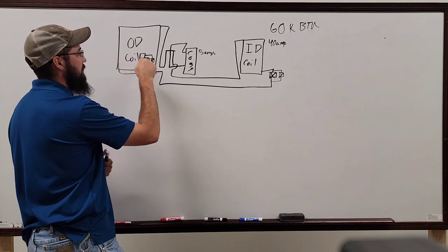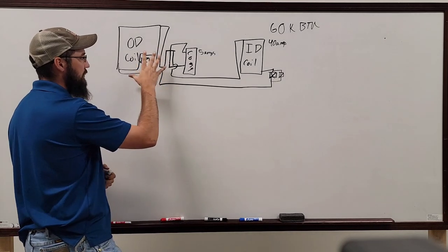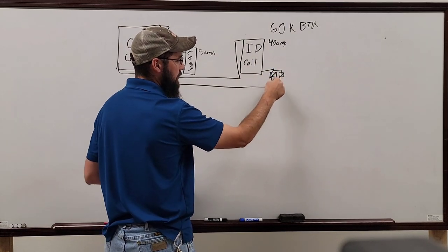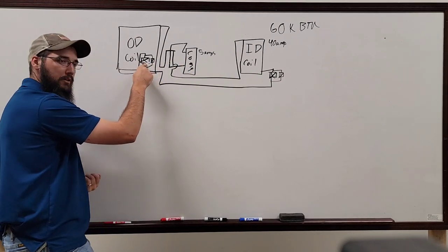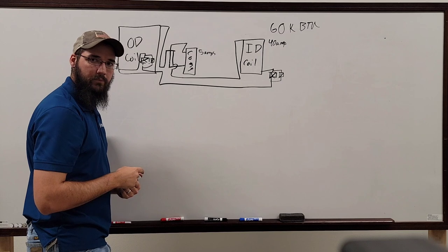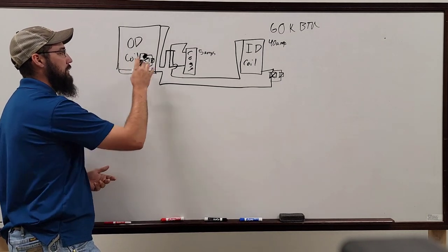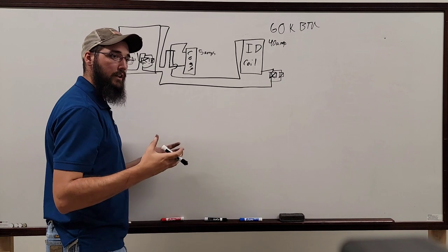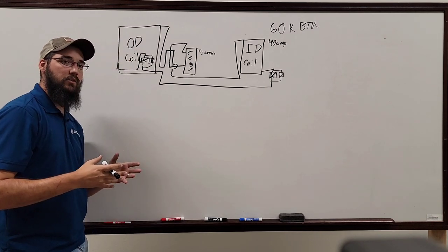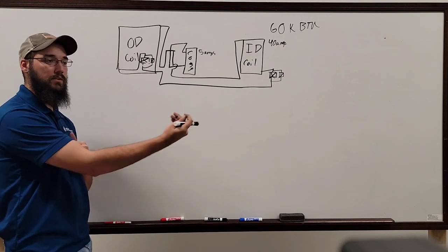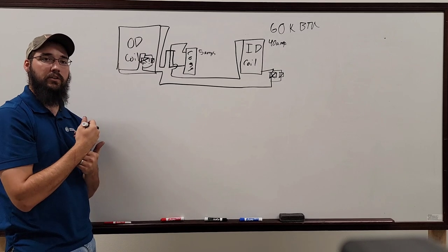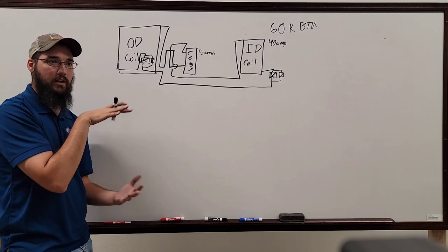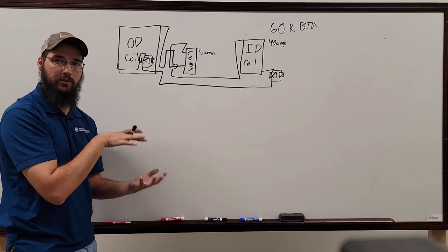So in that particular case, in cooling mode, this EXV or this metering device gets bypassed and we're flowing through this one. When we cycle over to heat mode, this metering device gets bypassed and we start cycling through this metering device and the outdoor coil. So we literally switch. These could be pistons, they could be TXVs. Some TXVs will internally check, or internally bypass, to where once it gets flow from the opposite direction, it will force the valve open and allow it to flow the other direction. Don't ask me exactly how that works. I just know that there's supposed to be some valves out there that do that.